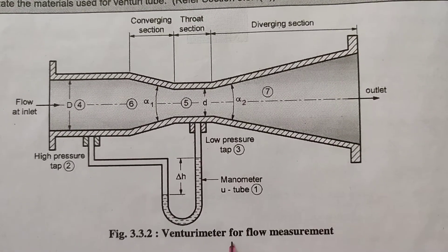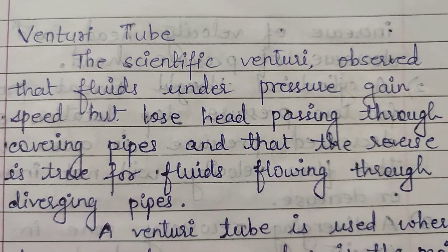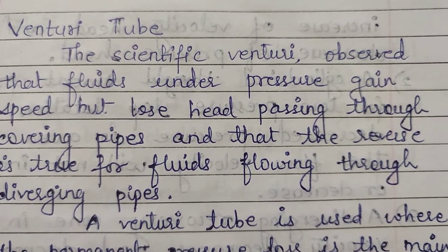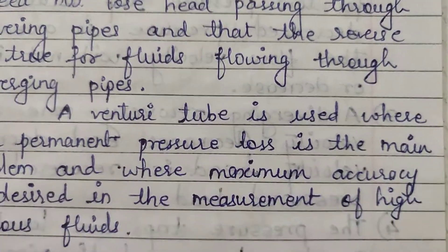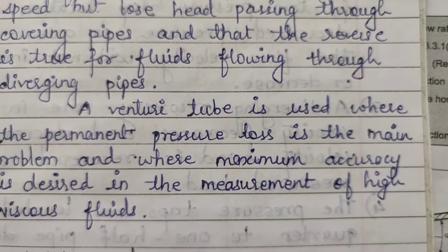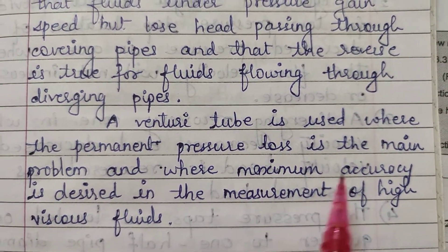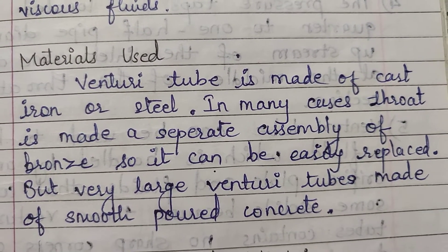First, we will see the Venturi flow meter. This is our diagram of the Venturi flow meter. The scientist Venturi observed that a fluid under pressure gains speed but loses head passing through converging pipes, and that the reverse is true for fluids flowing through diverging pipes. A Venturi tube is used where permanent pressure loss is the main problem and where maximum accuracy is desired in the measurement of high viscous fluids.